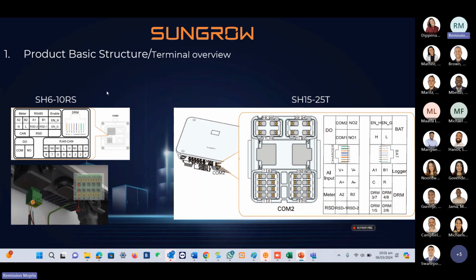Then this is the connection block for the communication part. For the battery, you can use a straight RJ45 and just plug it on the port, or use CAN high and CAN low on the green connector block. This is the green connector block. So basically you can connect the meter on A2, B2 and CAN high and CAN low on the green connector, or terminate the RJ45 communication from the battery and then plug it on the RJ45 CAN on the inverter directly, or just use a normal Ethernet cable. You can just take any Ethernet cable and plug it on the battery and plug it on the inverter. It will work just fine.